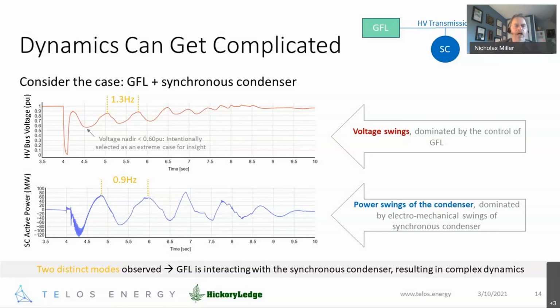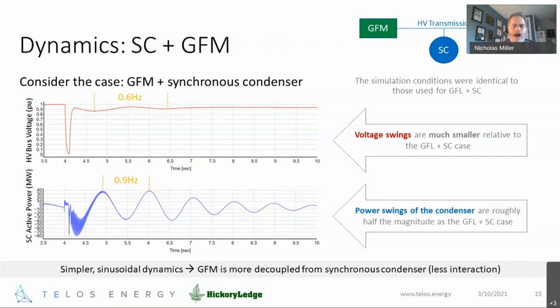So if we go on to the next slide, this is our apples to apples comparison, all of the things being equal, the same synchronous condenser. And let's talk about the lower trace. First of all, we didn't alter the natural frequency of that synchronous condenser against the rest of the system. It's still at about 0.9 hertz. Those swings are about half as much because they are not interacting anywhere near as much with the inverter. So you see the inverter does have some swings.